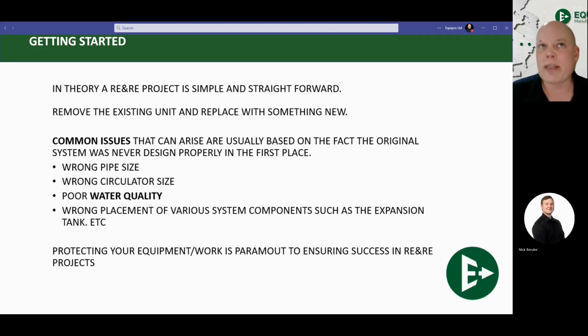So in order to get it right, according to the CSA B214, according to the code, systems must be designed, meaning that someone has to own the design of a system. And we'll get back to that here in just a moment. But the whole point of talking about these common issues is not to scare you away from it. In fact, we highly encourage you to give it a shot, but we want to make sure that you're protecting the equipment and protecting your work. When you change out a piece of a system, you own that piece now. You don't own the whole thing, but you own that piece. And if your mistakes in this area of isolating and addressing the system are done wrong, then that can lead to problems with your piece that you just installed, and then you're going to have to do all sorts of callbacks and work on the system. That's something that you could have avoided in the first place.